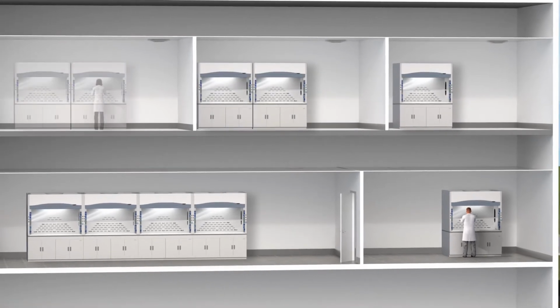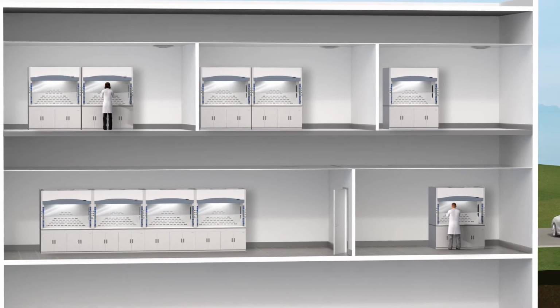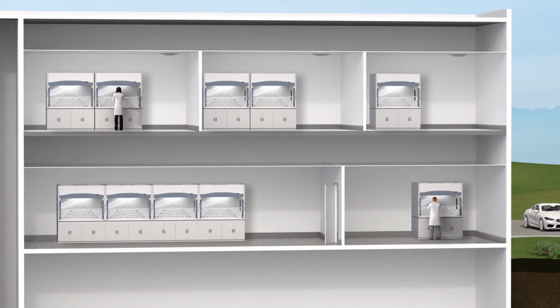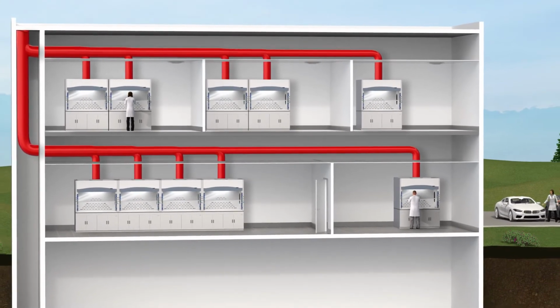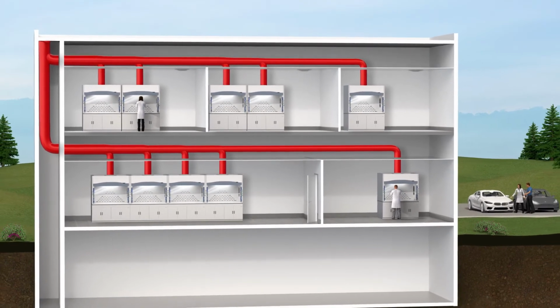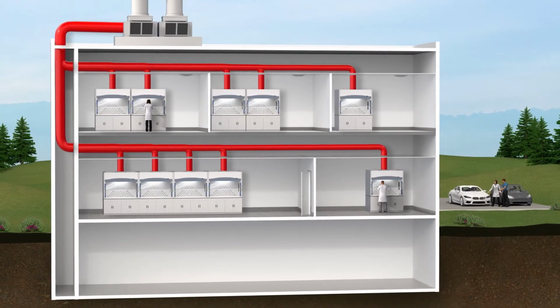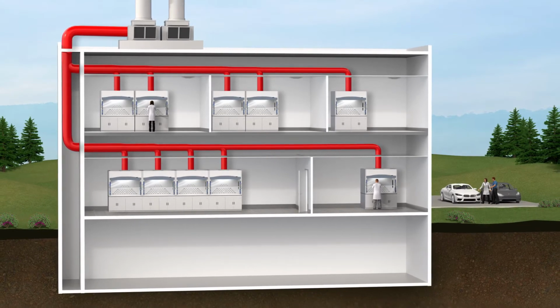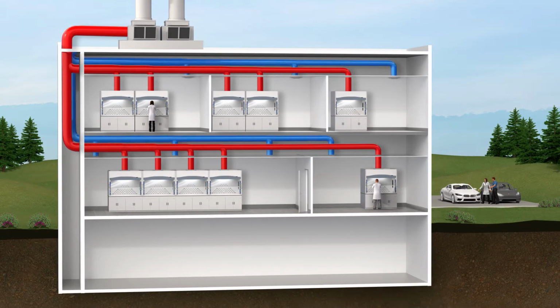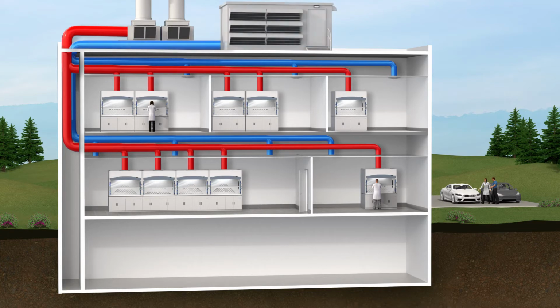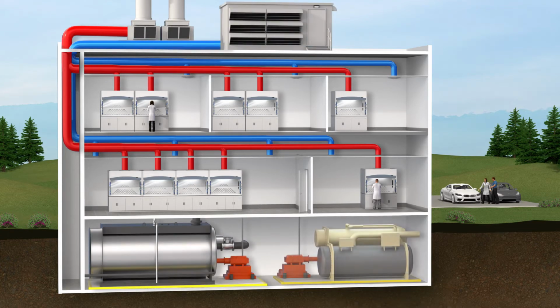Chemistry labs need fume hoods so researchers and students can safely handle hazardous chemicals. But those fume hoods need exhaust ducts, airflow control valves, and exhaust fans to make them work correctly and safely. Labs with many ducted hoods will need even more supply air, requiring larger air handling units, boilers, chillers, and cooling towers to pre-treat all that air and deliver it into the labs. As a result, both construction costs and annual operating costs are very high, predominantly due to the use of ducted fume hoods.